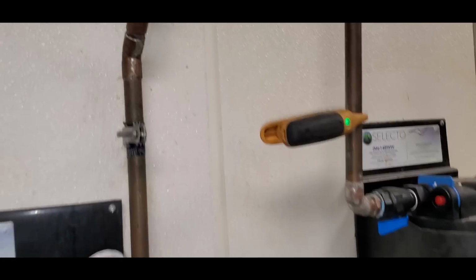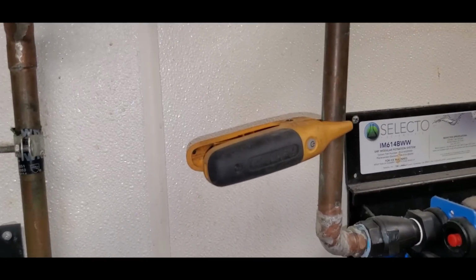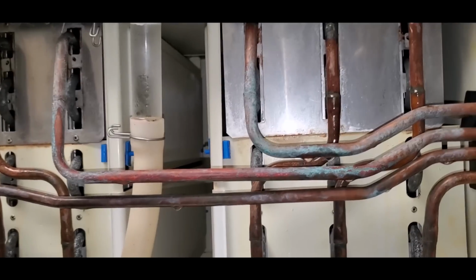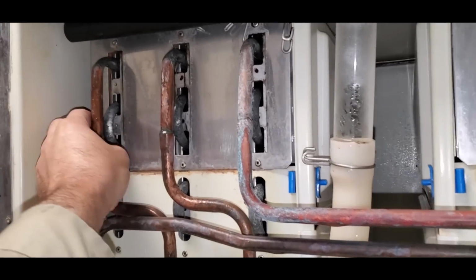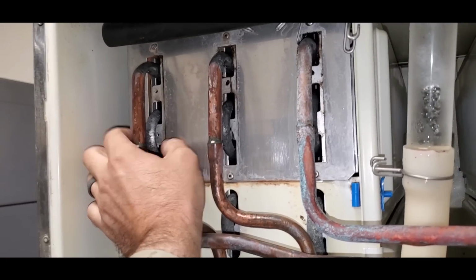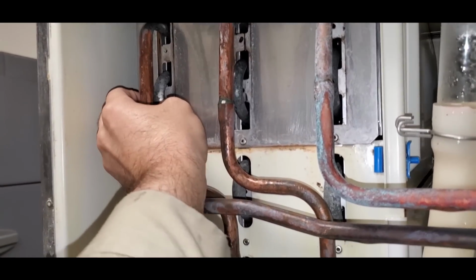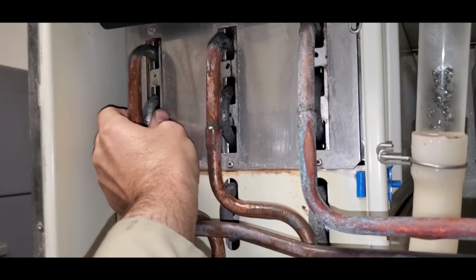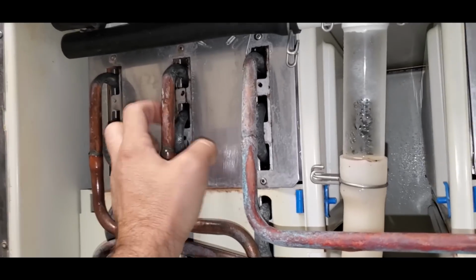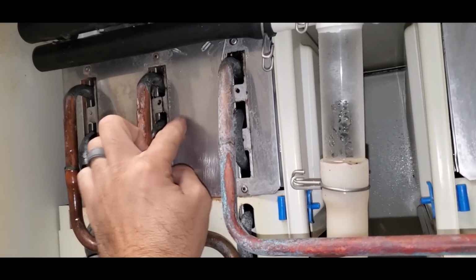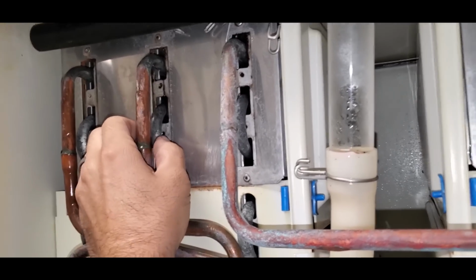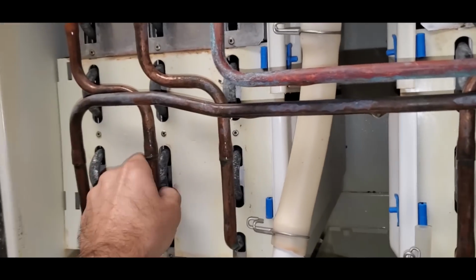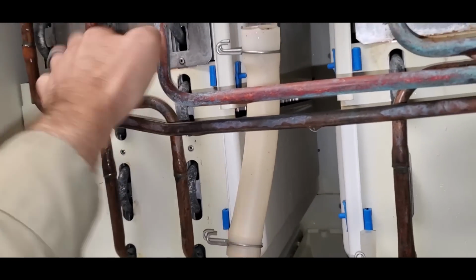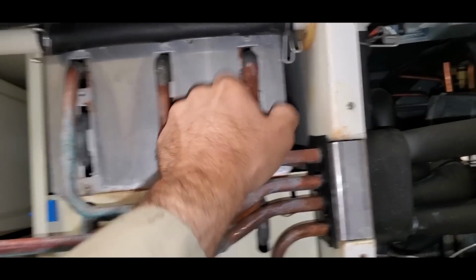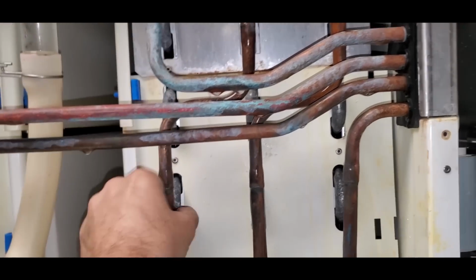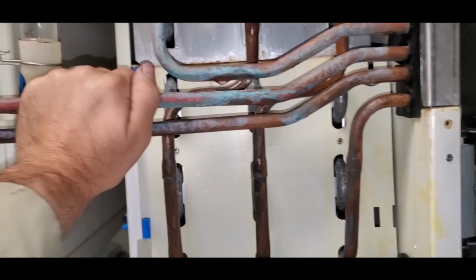I was curious if we have hot water coming to the machine, but I'm not sensing it. Whenever we have a warm evaporator, I always want to check for plate separation. So grab the stationary tube and try to move it up and down - don't mistake the natural flex for separation, but you don't want to see this tube move within the evaporator. I just check them all, but it's best to check when the evaporator is warm, right at the start of a defrost, like right now since it just turned on.